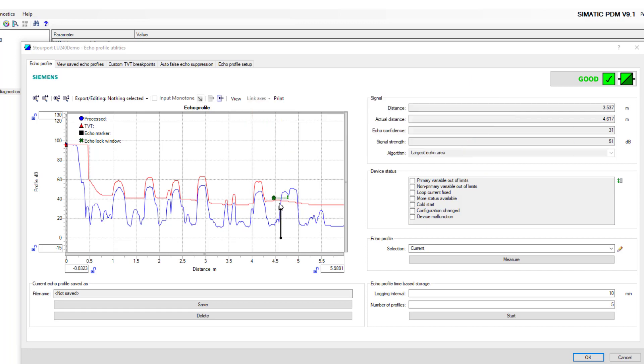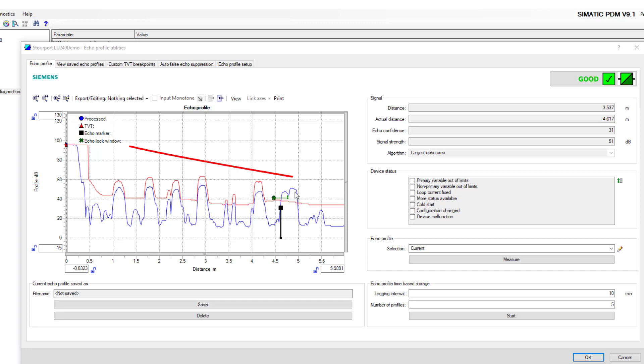Here you have the echo profile after we've done the auto false echo suppression. You can see it's moved the red line above all the obstacles enabling us to lock on to the correct level. I quite often get asked what happens when this signal travels up into this red zone. The beauty of ultrasonics is as this gets closer, it's actually going to get higher in amplitude and stronger because it's got less distance to travel. The more obstacles our level goes past, the more signal we're getting back because less of it is being absorbed by the obstacles. As we start getting up we should see this double in size and these false echoes really pale into insignificance.